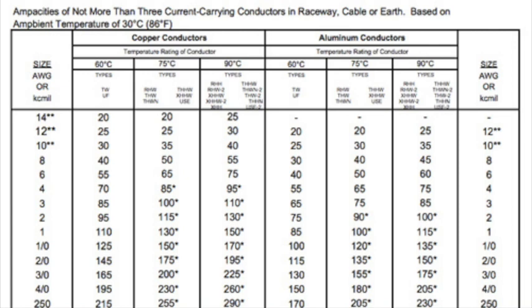You may have seen published tables showing the maximum amount of current that a wire can pass. This is of little use for handling voltage drop issues. The voltage drop issue will occur long before the maximum current point is reached.